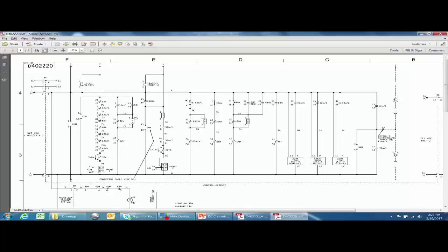As long as the 52Y is picked up, that contact is open and you cannot close the circuit breaker. This is the anti-pumping scheme. Pumping a breaker is when you have a standing trip and a standing close — it goes trip, close, trip, close, then stops to recharge the spring, then resumes until something fails — presumably burning up the close coil.